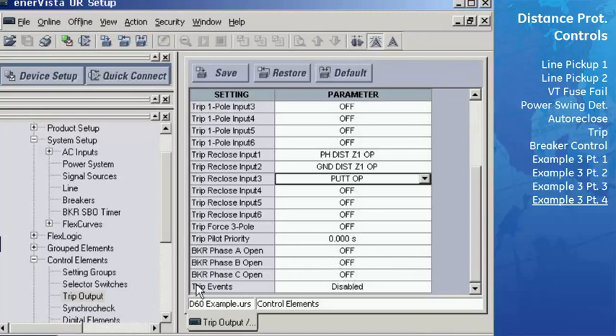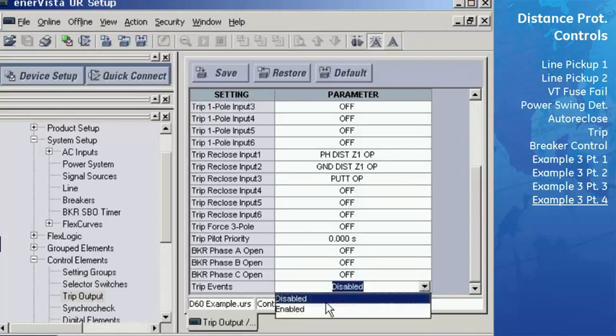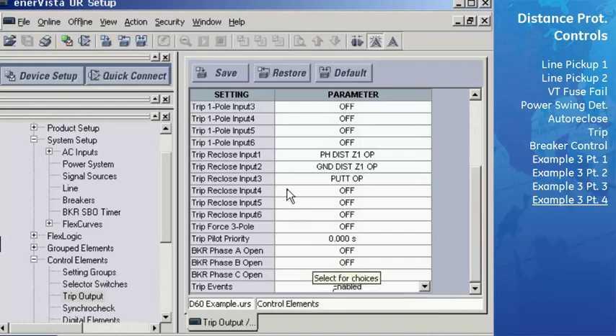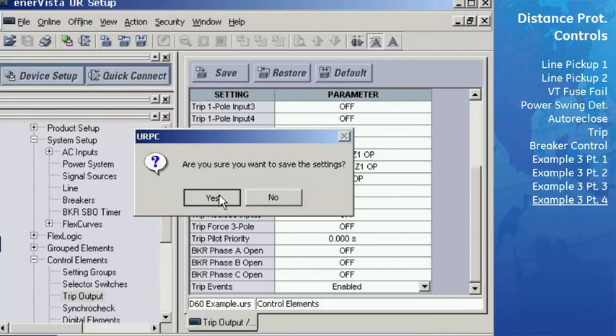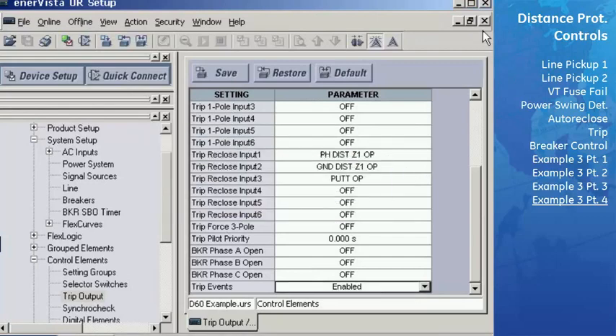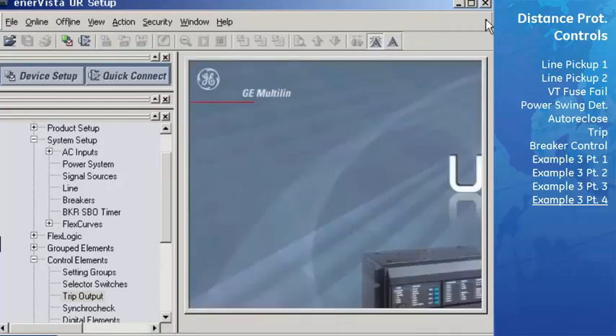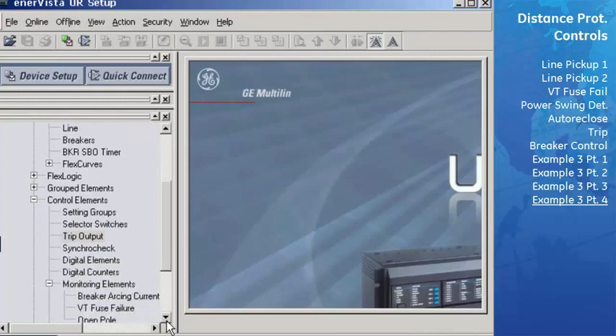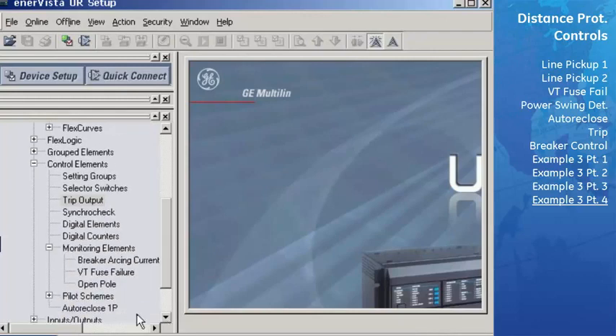Enable the trip event field so that the trip output operation shows up in the event record. Save these settings to the file and close this window. Now we'll configure the Auto Recloser scheme. Go to Control Elements, Auto Reclose 1P.